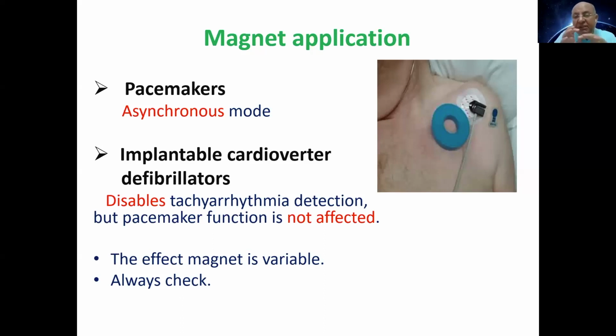But the effect on the CIED is different for the pacemaker and the ICD. This is a very important point, please. If you put a magnet on a pacemaker, it will change the mode to asynchronous mode, as we said before. What is asynchronous mode? Non-sensed pacing, non-sensitive, regardless of the intrinsic activity. The magnet will put the patient in asynchronous mode.